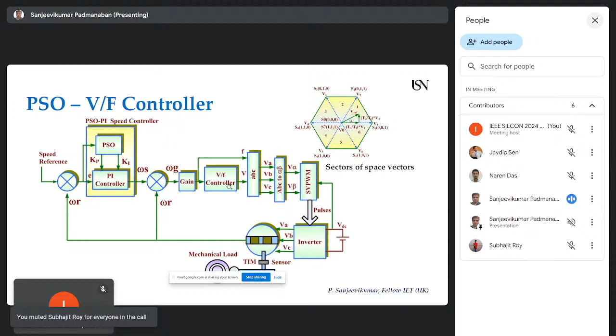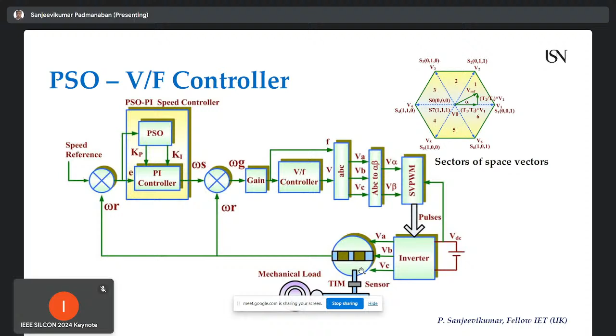We have a V/F controller here, which is a lookup table with frequency on the x-axis and voltage on the y-axis. For example, if the frequency is 0, the output voltage is 0. If it is 50, it is the rated voltage of the system. Then that is given to an ABC control to convert all the three phases into the stationary reference frame for controlling active power and reactive power, or I can say torque and flux. We give that to the space vector modulation that will regulate the inverters to the required speed. So with all these conditions, you are able to regulate the induction drive to the appropriate level from the different powers.